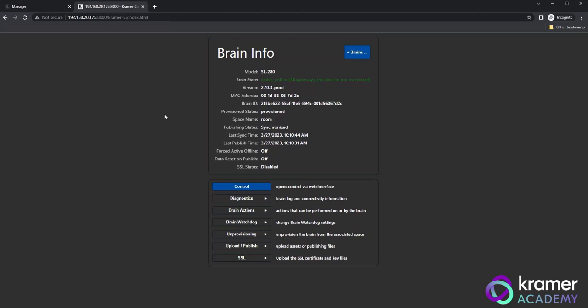If you see a yellow or orange status, that means one or more of the controlled devices is not communicating with the brain. If this happens, check the IP address or login details of the controlled equipment within the builder gateways.